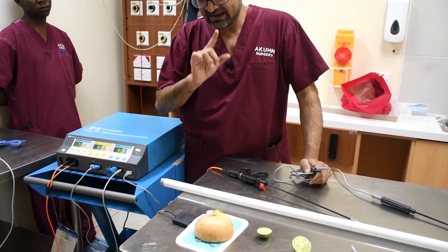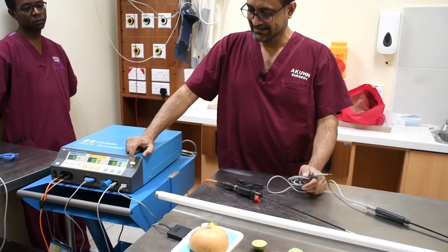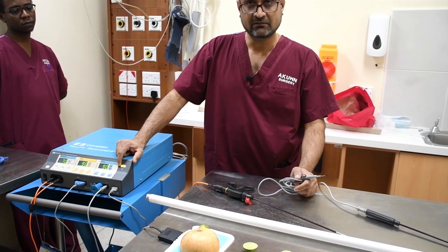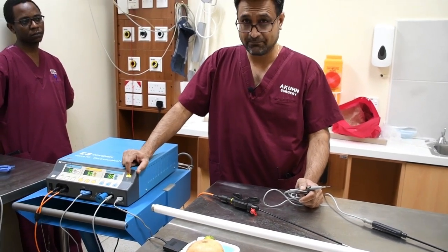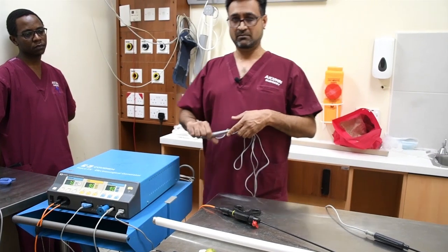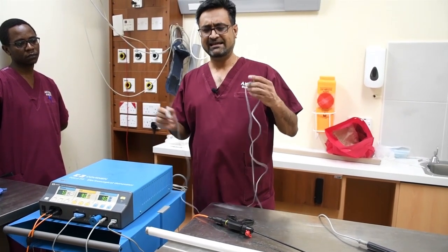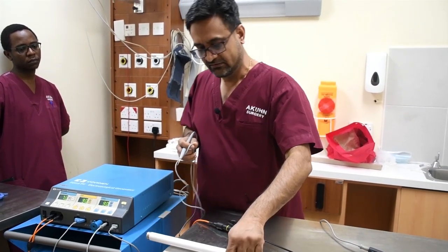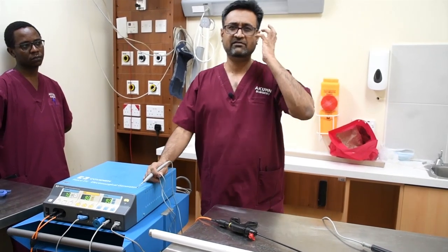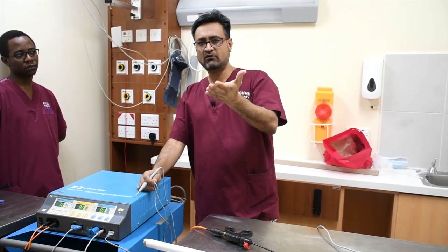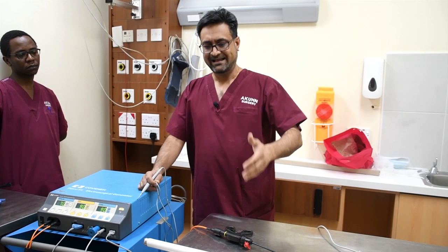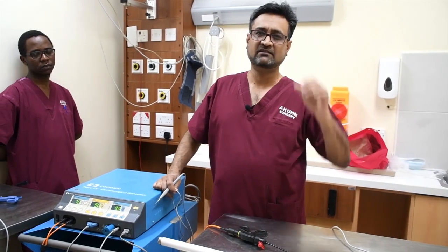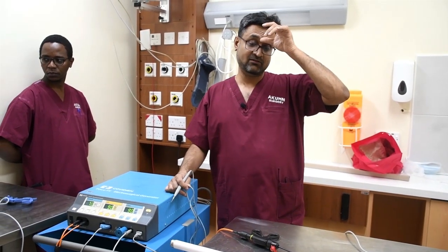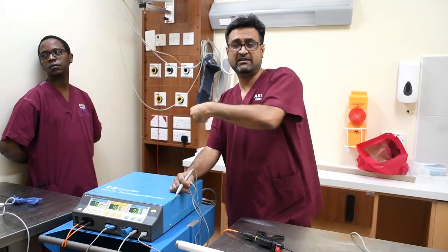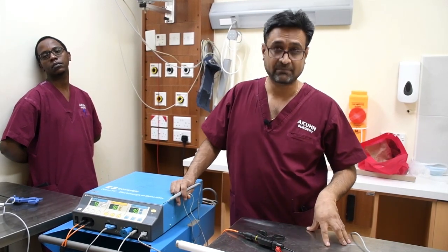If there is a break anywhere in this circuit, then this will not turn green, it will turn red and beep, telling us that there is a problem. So this is with the newer machines. In the past, these return electrodes were of different types. We have the metallic one, we have the silicone one, which is a black rubber, and we have these ones which are dispersive, and they have automated monitoring telling us whether it's a complete circuit or not.